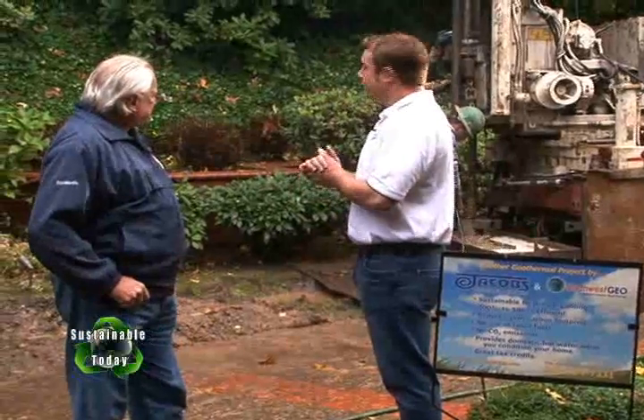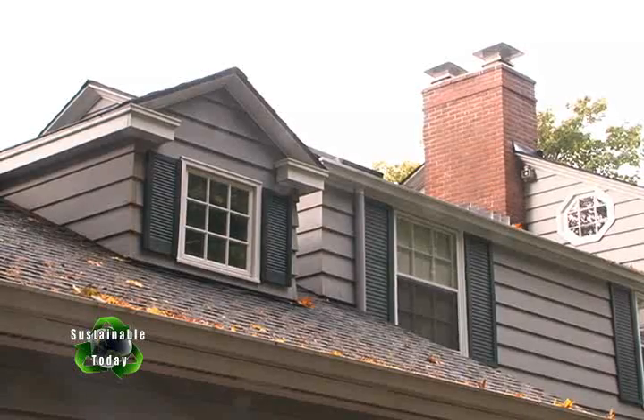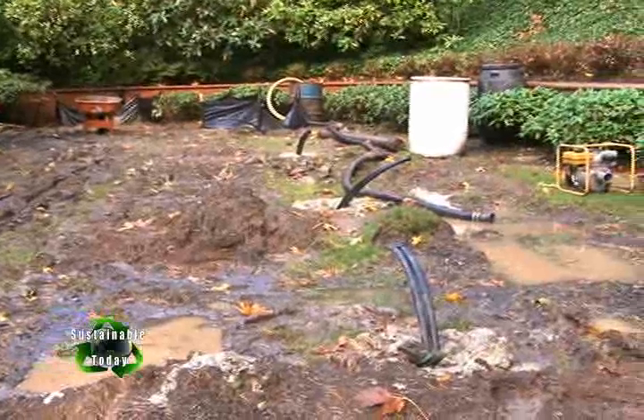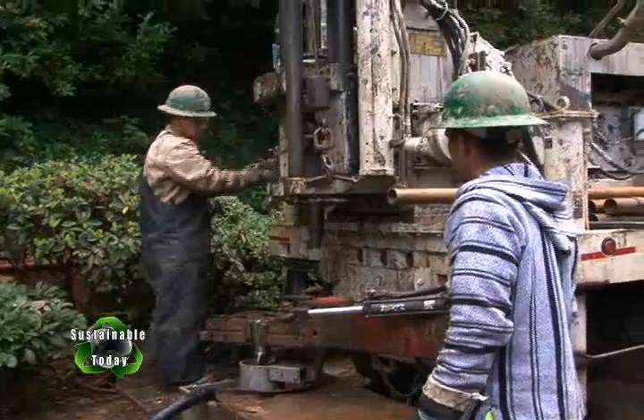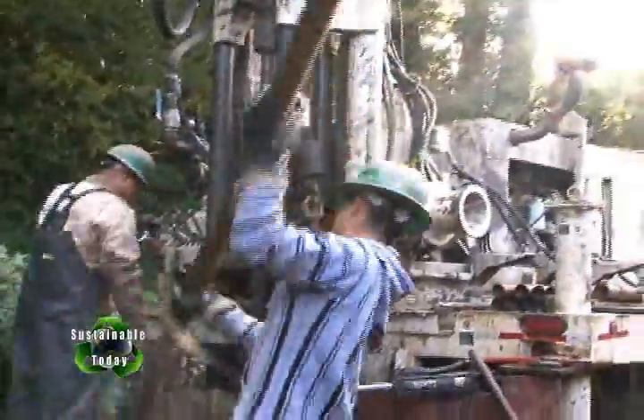What we have here is a drill rig that's going to be putting in a 150-foot ground loop. We've got an older home built in about 1940. He's actually doing upgrades — an insulation upgrade. He's got a furnace on the lower floor and a furnace on the upper floor. He has a total of eight 150-foot boreholes on this particular project, and we're going to link four loops up to the lower system and four loops up to the upper system.